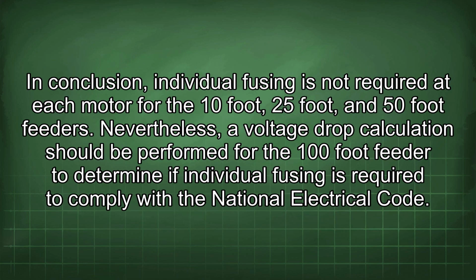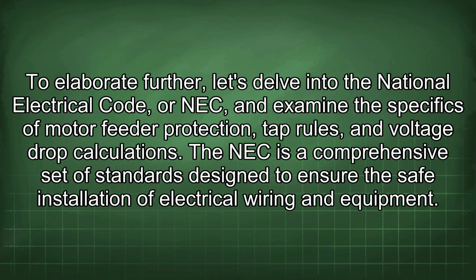In conclusion, individual fusing is not required at each motor for the 10-foot, 25-foot, and 50-foot feeders. Nevertheless, a voltage drop calculation should be performed for the 100-foot feeder to determine if individual fusing is required to comply with the National Electrical Code. To elaborate further, let's delve into the National Electrical Code, or NEC, and examine the specifics of motor feeder protection, tap rules, and voltage drop calculations.